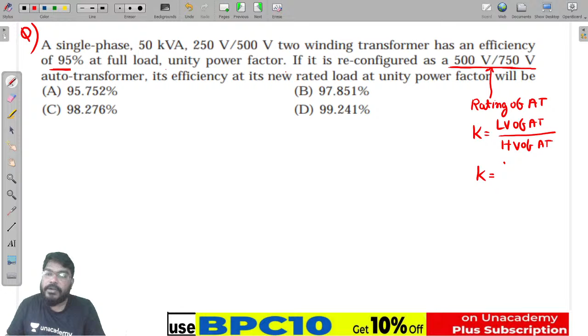So K is done. But what about the efficiency when it is reconnected as an auto transformer? As I already mentioned, if it is reconnected as an auto transformer, the total losses remain the same, but the kVA rating will be different.